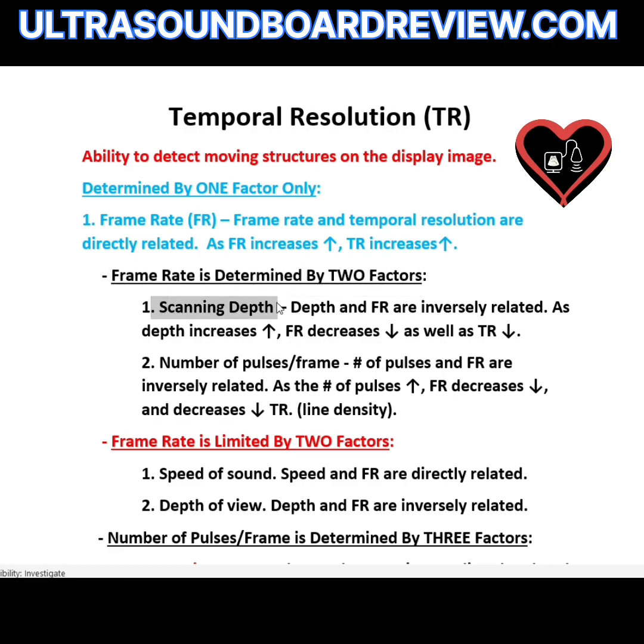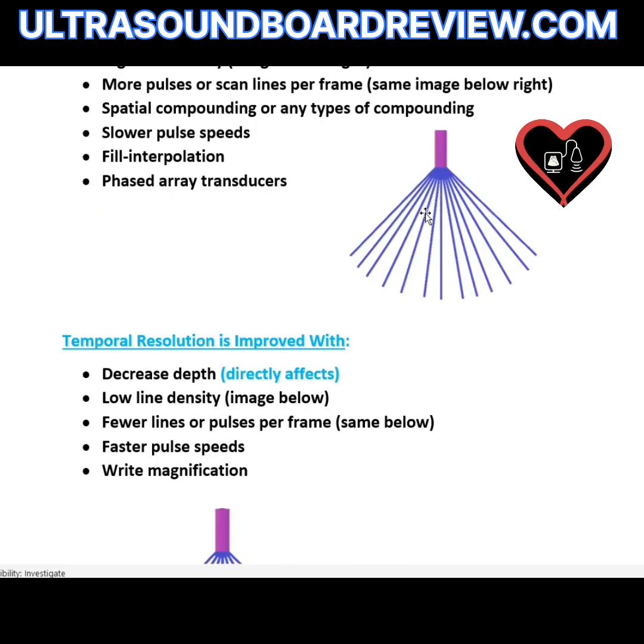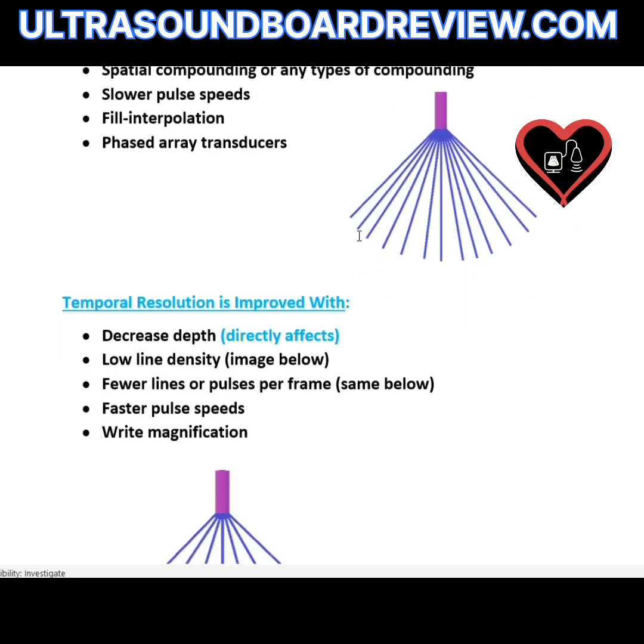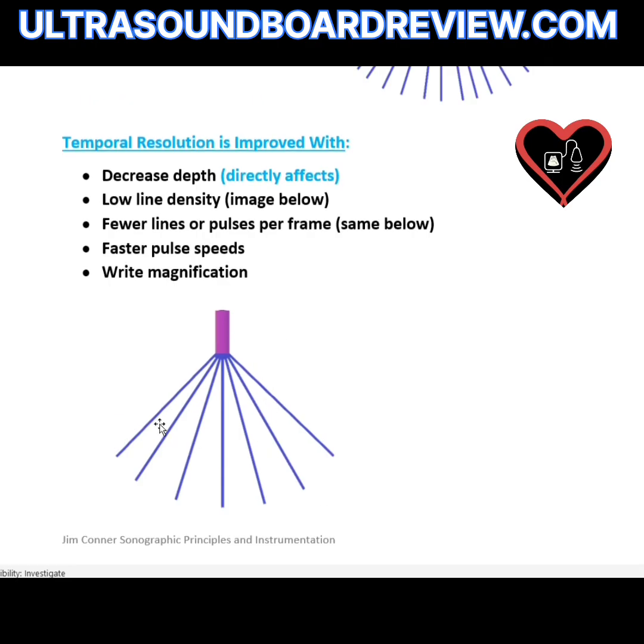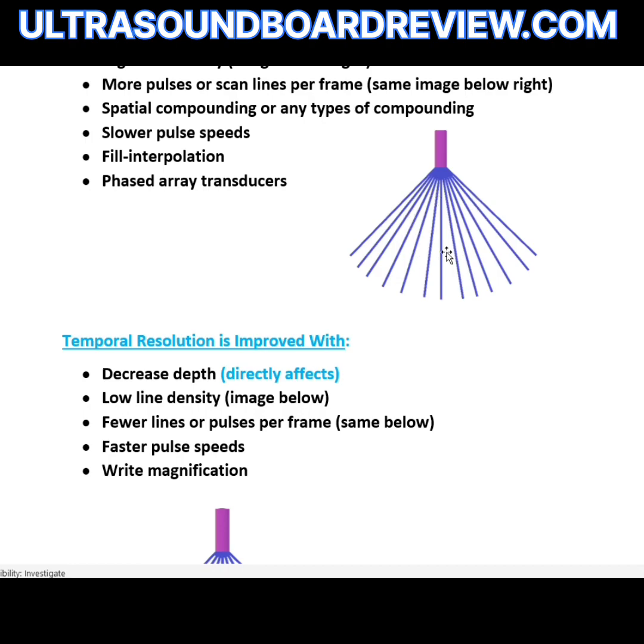Frame rate is determined by two factors. The first is scanning depth — depth and frame rate are inversely related, so as depth increases, frame rate and temporal resolution decrease. The second is the number of pulses per frame, which is also inversely related to frame rate and temporal resolution, so as the number of pulses goes up, temporal resolution and frame rate go down. In this diagram, each line represents one pulse. The image with fewer scan lines will have the best temporal resolution and frame rate because there are fewer pulses per frame.